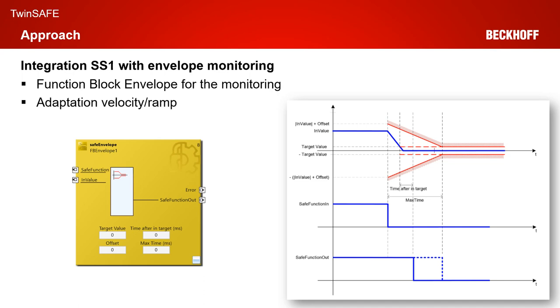There is a maximum allowed time to get down to the target value. If you violate that maximum time, the output goes to false. As soon as the input value is within the target region, there is a configured amount of time called 'time after in target', and after that time, when the input value stays within the target range, the output goes to false. We have to adapt the velocity and the ramp to match our current application.